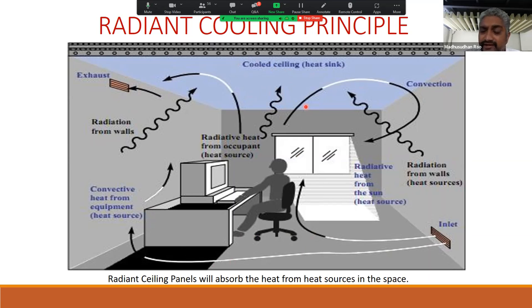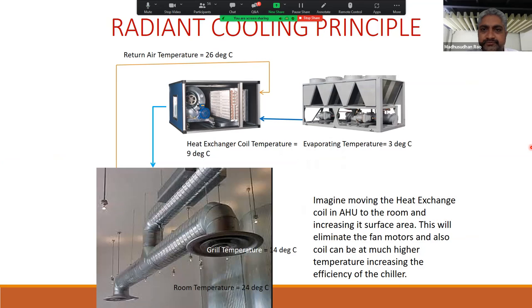So at the end of it, even though per square meter you may get higher output, the actual amount of square feet that you get on the ceiling may be lower. So net, the absolute amount of heat exchange that you would actually get from ceiling and floor may be the same. Okay. And it's much easier to manage a floor-based cooling system. However, we have done all. I'll show some of the installations that have been done so that you can visualize it.